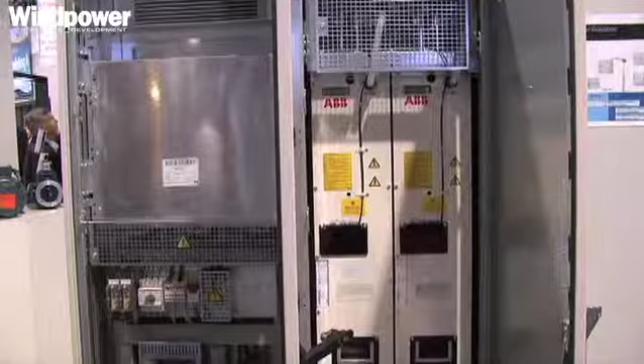A couple key points about this drive: it's a full power converter using a modular approach, so each module is an individual three-phase module. In this case, we have a liquid cooling enclosure, making it an ideal application for offshore type wind turbines. It's a completely sealed cabinet, fully isolated from the environment, and with liquid cooling, the power density of these cabinets is better than air-cooled versions.